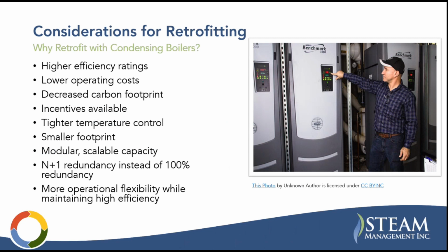So why would you retrofit with condensing boilers? Obviously, you're looking for higher efficiency ratings in your conventional hot water boiler. You want to lower your operating cost. You want to decrease your carbon footprint. There are utility incentives available for these units. They give you tighter temperature control than your older boilers, although advanced control on a new conventional boiler would probably be similar. They have a smaller footprint. They're sort of modular, so you can scale your capacity. And oftentimes when you're retrofitting, because they have a smaller footprint, it leaves room for additional boilers.